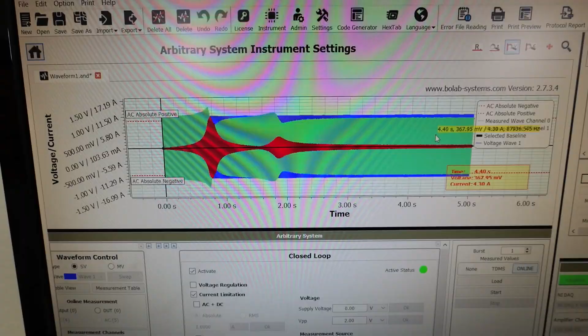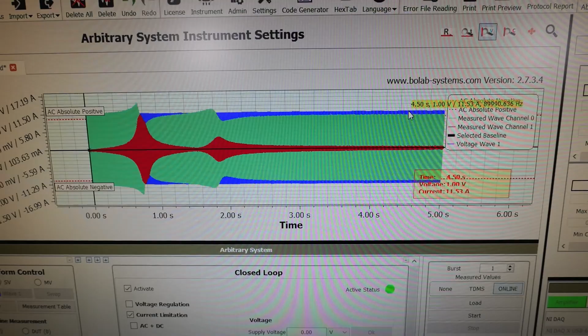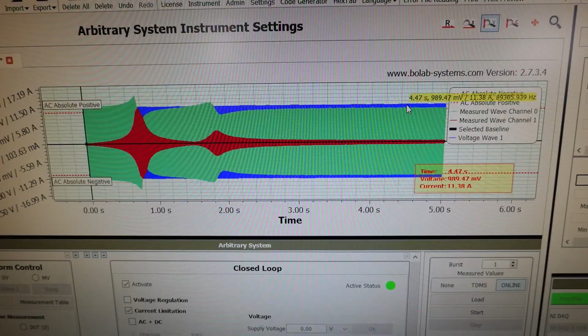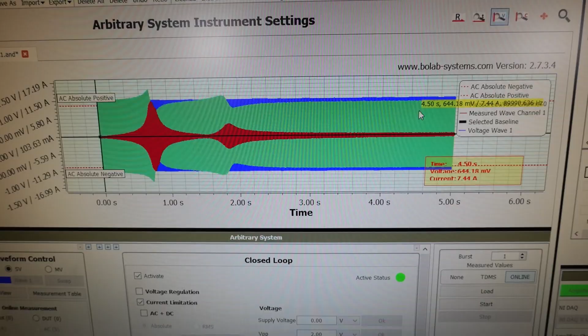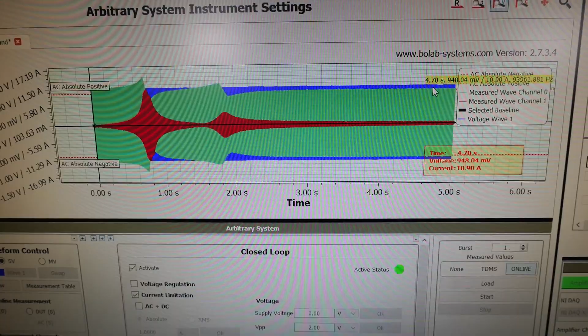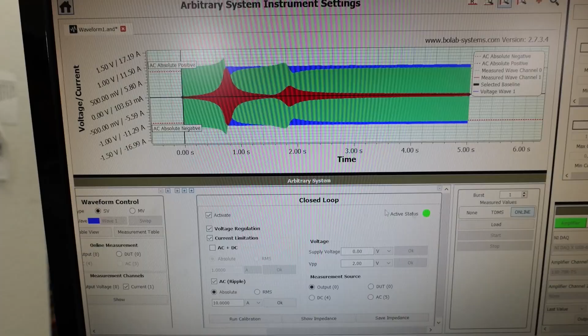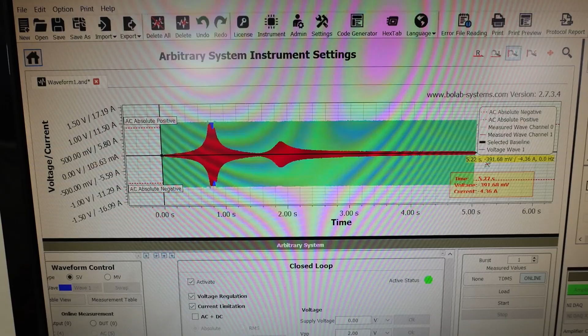The next step is, the standard says, here you see the blue sine waveform, this is the reference waveform, the given waveform, and the green is the measured voltage. Now you see the difference: at higher frequencies there is a voltage drop on the lines, and the standard requires that this voltage drop must be eliminated. This is not allowed. So we do the next step and say voltage regulation. Additionally, we do the same thing again. We load the waveform to the instrument and start again. Now you see the voltage stays constant at the required level, and this is exactly what is required in the standard.